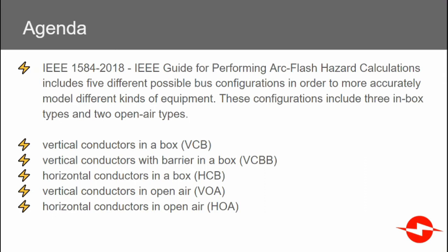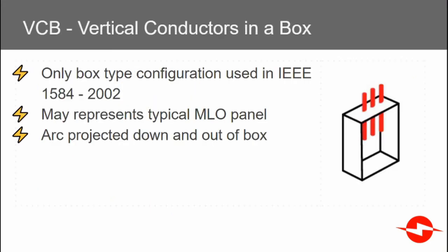These configurations include three box types and two open air types. The first box type, vertical conductors in a box, was the only type of configuration used in the previous version of 1584. This may represent a typical main lug only panel. The arc is projected down and out of the box.